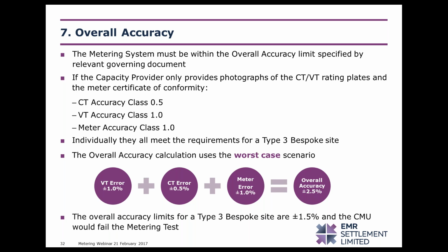So if we used 1% for the voltage transformer, 0.5% for the current transformer, and 1% for the meter, the overall accuracy is within plus or minus 2.5%. The rules specify that the overall accuracy limit for a type 3 bespoke site is 1.5%, and in this instance the CMU would fail the metering test on overall accuracy. You do have the option of compensating the meter for any transformer errors, but you do need error certificates to be able to justify that adjustment. It is imperative that when submitting information, for at least 2 out of the 3 components of the metering equipment, you provide evidence of the actual error to ensure that you're always within the overall accuracy limits.